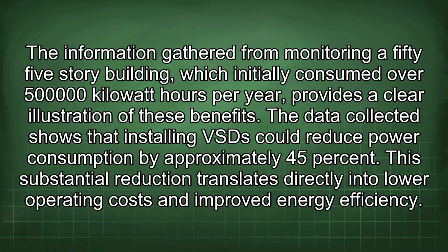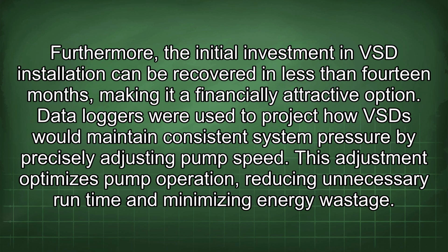months. The information gathered from monitoring a 55-story building, which initially consumed over 500,000 kilowatt-hours per year, provides a clear illustration of these benefits. The data collected shows that installing VSD could reduce power consumption by approximately 45%. This substantial reduction translates directly into lower operating costs and improved energy efficiency.